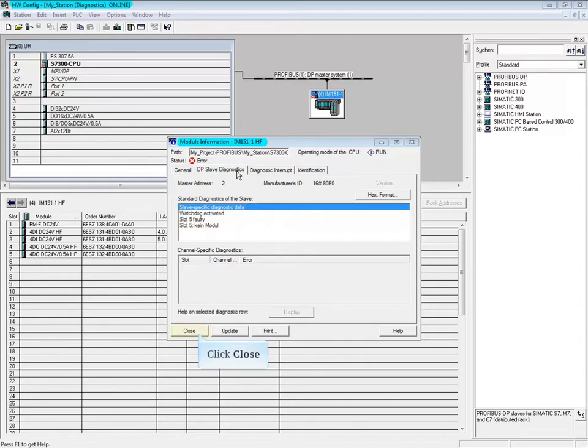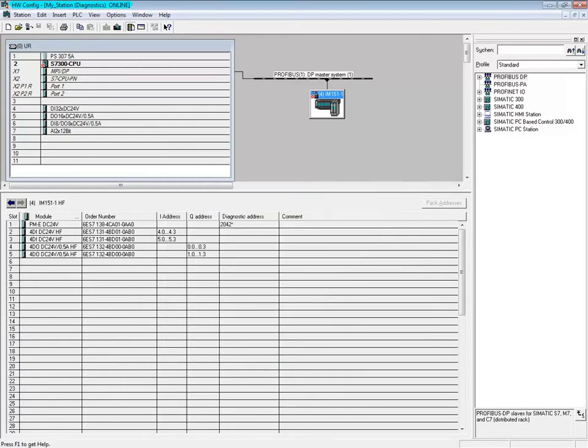Now it's time to have a look at the physical station and see what's wrong. After inspection, it turns out that the submodule had been hit with an object and broken. The wiring terminal module, interestingly, was not damaged. A new submodule was plugged in and the problem fixed. To update the hardware configuration view, press the F5 key. This concludes the video on troubleshooting a signal module failure on the ET200S system.